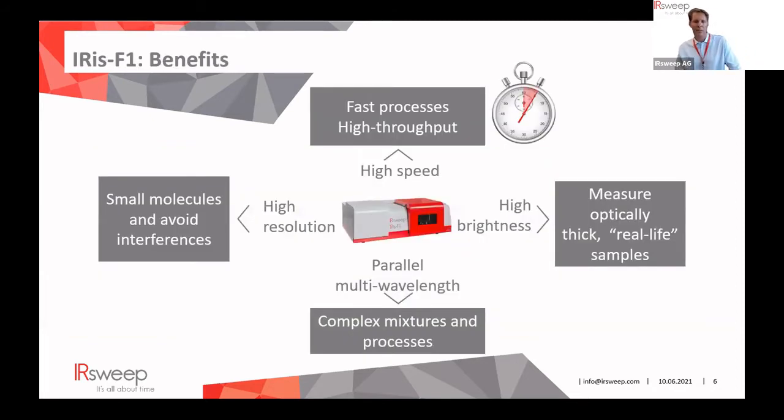There are several benefits when talking about QCL frequency combs. One is the speed advantage — the focus of this talk — with high time resolutions on the order of milliseconds or even microseconds. Another is brightness: the dual comb spectrometer uses strong laser sources which are orders of magnitude stronger than thermal light sources such as the globar. It can also measure complex mixtures using multiple laser lines simultaneously. Finally, there is a high resolution version of the Iris F1 capable of recording 0.001 wavenumber resolution in a few minutes.